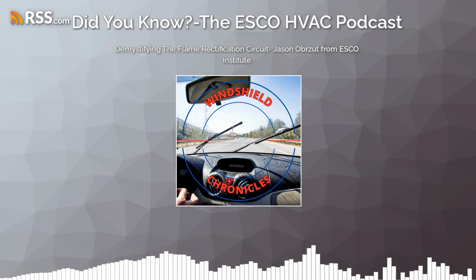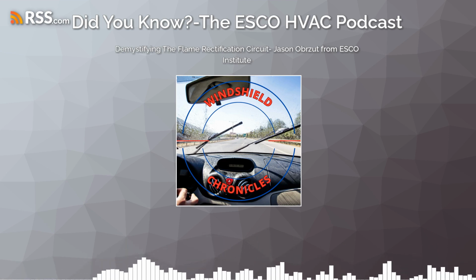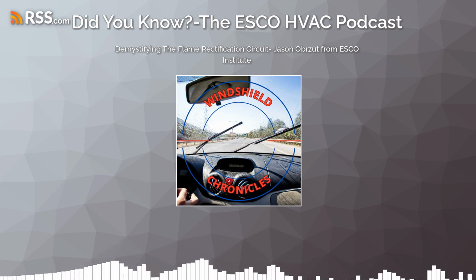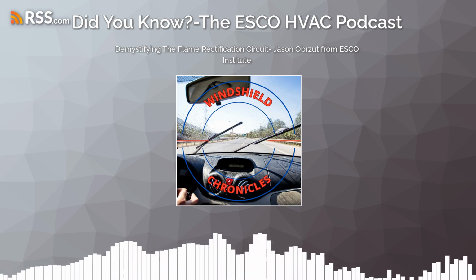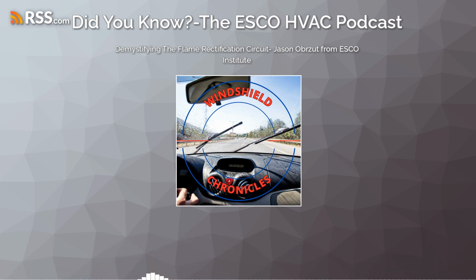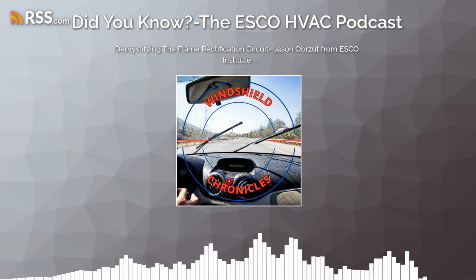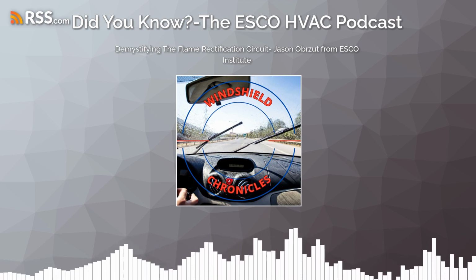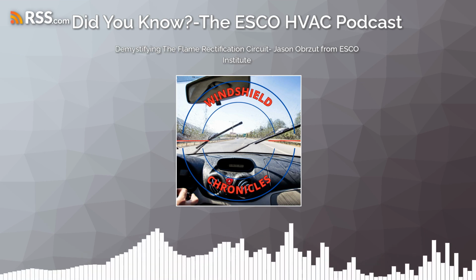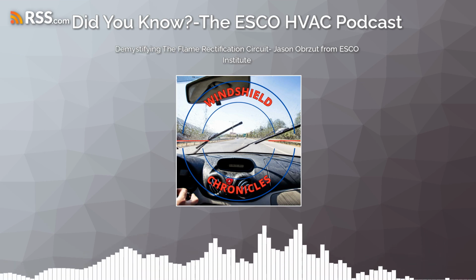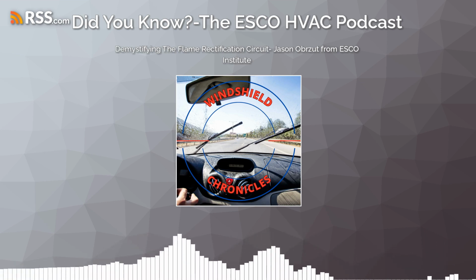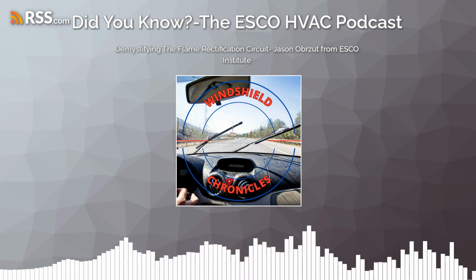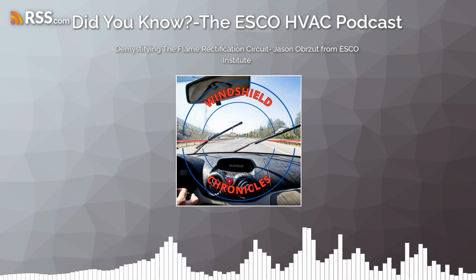And the purpose for that blower is to induce into the heat exchangers, the combustion air and the gases. But we also have a safety switch in there that needs to make sure that our flue is clear. We have the proper airflow through the heat exchangers, and that's that safety, that pressure switch. So when that inducer comes on, the pressure switch is going to close. And as the board, I'm going to get a signal from that pressure switch to say, hey, everything's a go, move on to the next step.